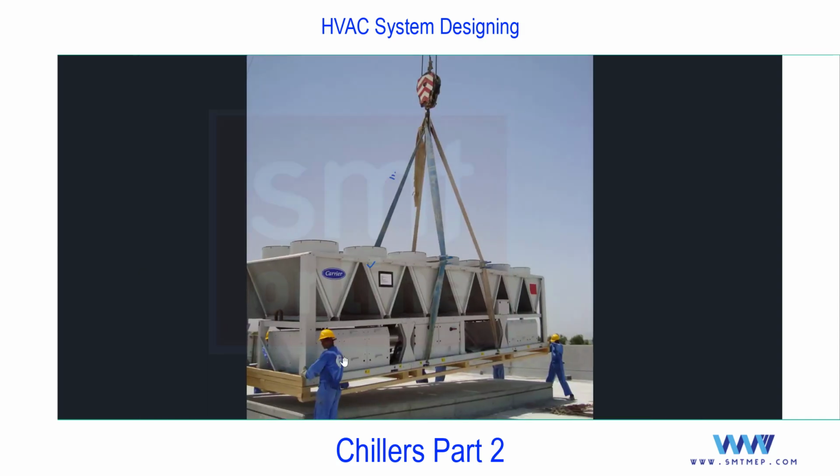Now you see, here in this chiller, here 3 cabinets, here 3 cabinets, so a total of 6 compressors. And in between, this is the electrical control, and above that you'll find all the condensers, and on the top you'll find the fans. So with this construction, you can identify an air-cooled chiller, and we place it outside, because in a water-cooled chiller you'll not find the fans. In an air-cooled chiller only you'll find the fans, because the major difference between air-cooled and water-cooled is the condensing side only. Okay, we'll do the conclusion at the end. Let me proceed.